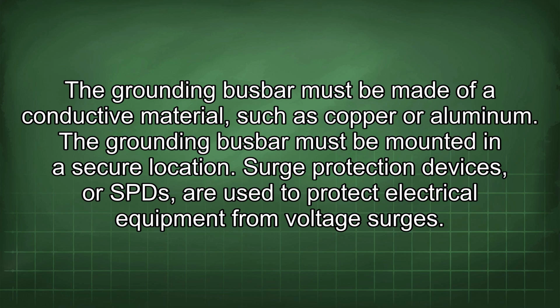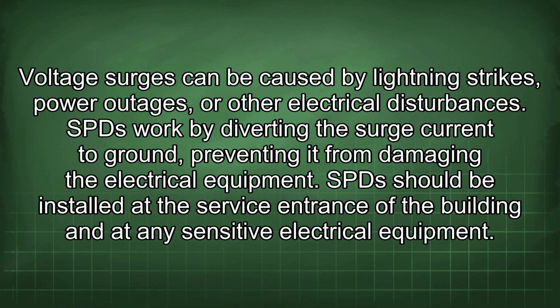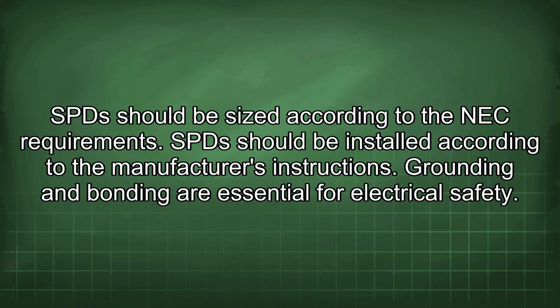Surge protection devices, or SPDs, are used to protect electrical equipment from voltage surges. Voltage surges can be caused by lightning strikes, power outages, or other electrical disturbances. SPDs work by diverting the surge current to ground, preventing it from damaging the electrical equipment. SPDs should be installed at the service entrance of the building and at any sensitive electrical equipment. SPDs should be sized according to the NEC requirements. SPDs should be installed according to the manufacturer's instructions.